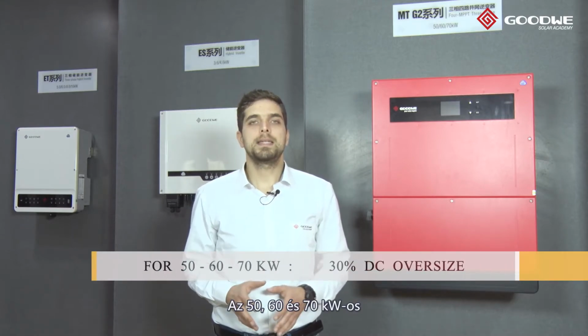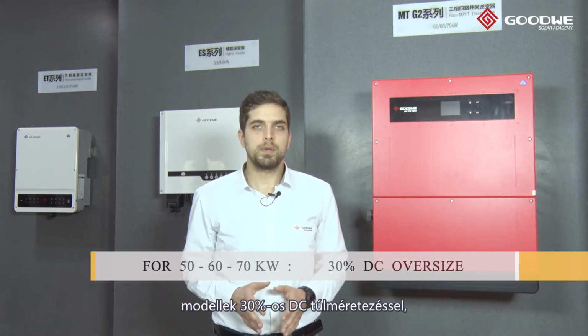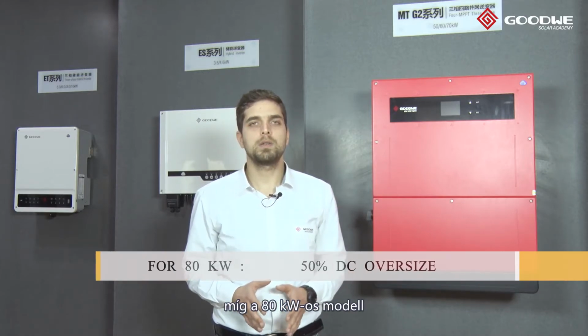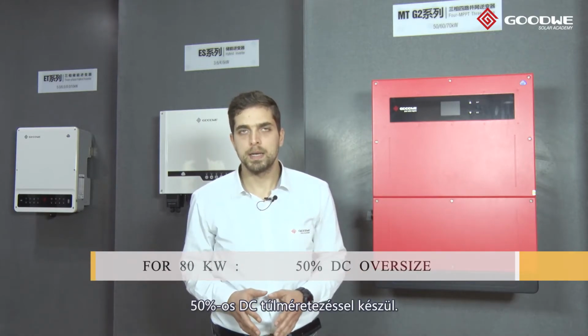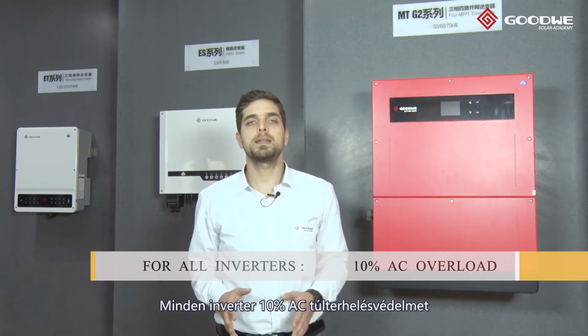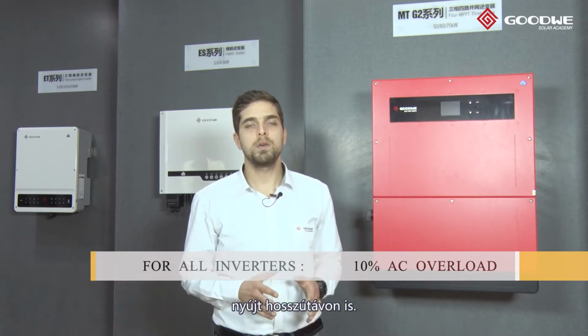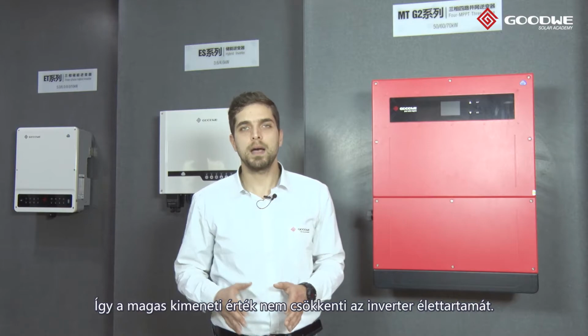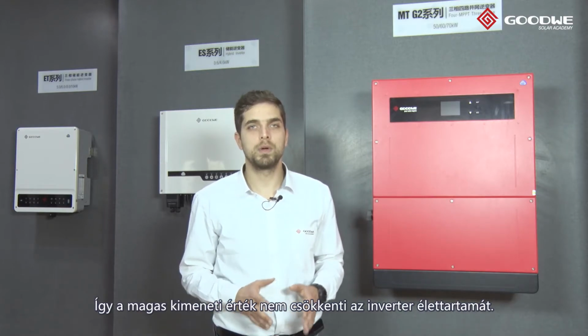For 50, 60 and 70 kilowatts, we have 30% DC oversize, and for 80 kilowatts, we have 50% DC oversize. And for all inverters, we have 10% AC overload ability. And this AC overload is for long term. That means this high output won't affect the lifespan of your inverter.